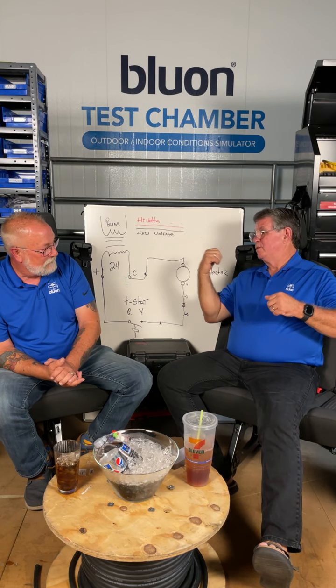I always go to the thermostat because of the transformer, because I want to make sure I've got voltage. And then I can turn around and jump it at the air handler, and if I jump R to G and the fan comes on, okay, I've got some good stuff going on. If I jump R to the one side of the wire going out to the condensing unit and it comes on, okay, great. So I can kind of work my way back.